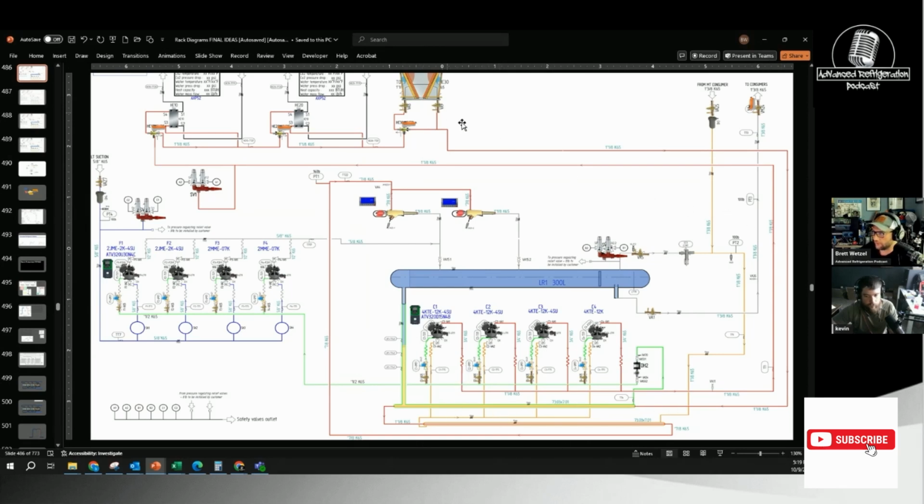The line coming out of the gas cooler, it's desuperheated, rolls through this little heat exchanger. It's like a tube and tube, correct? Yes, it's like one of the case ones you would see. Okay, gotcha. And then once it goes through there, it goes through another heat exchanger, and if you look, that one actually goes to the suction. Once it goes out through this second heat exchanger, which is actually for the suction, it goes back up and into these little valves right here.